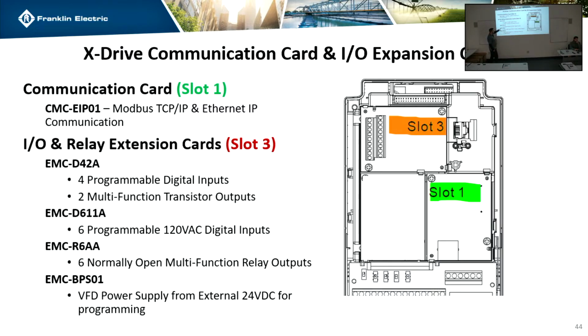There's also an output card, which is 6 open multifunction outputs, and then you can get one that has a separate power supply. I need to look up what the rating is for that. My guess is it's going to be the 150 milliamp, but I'll have to verify.